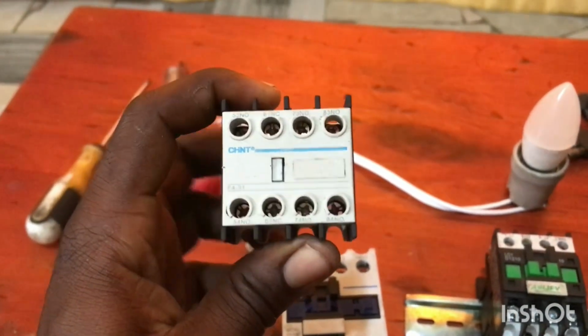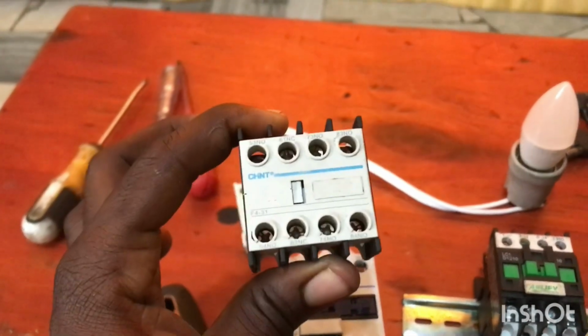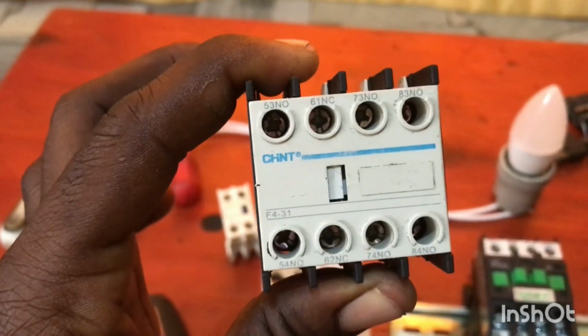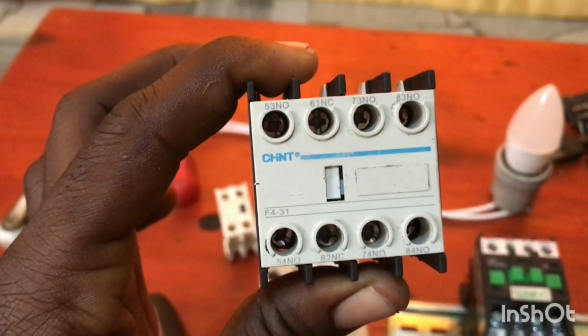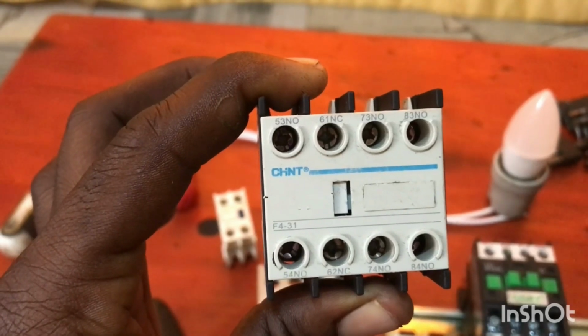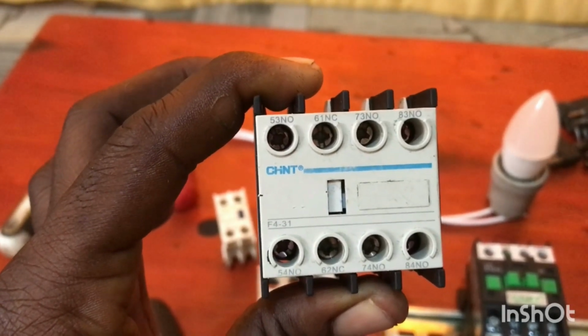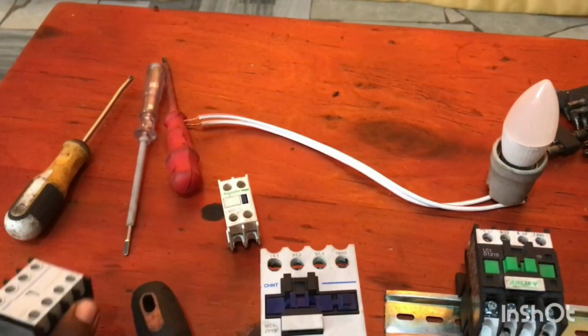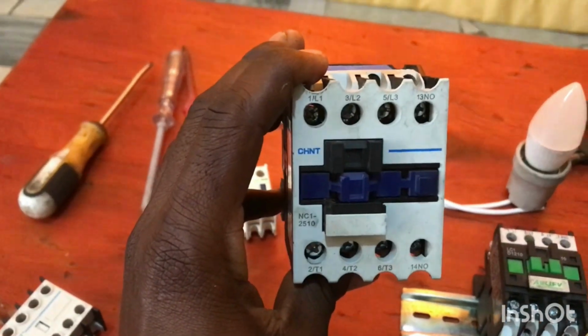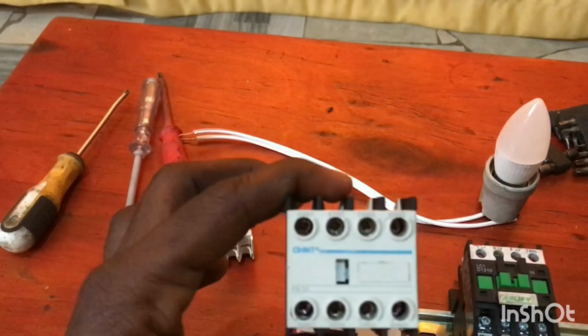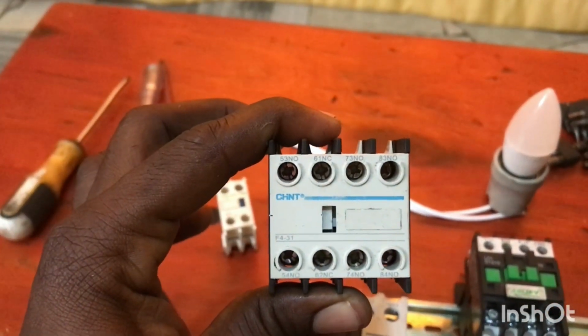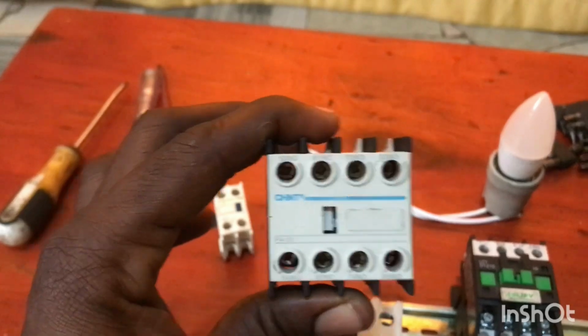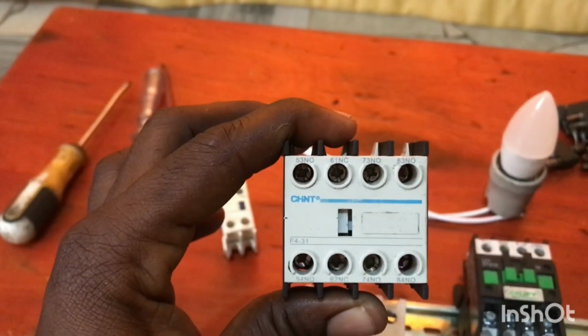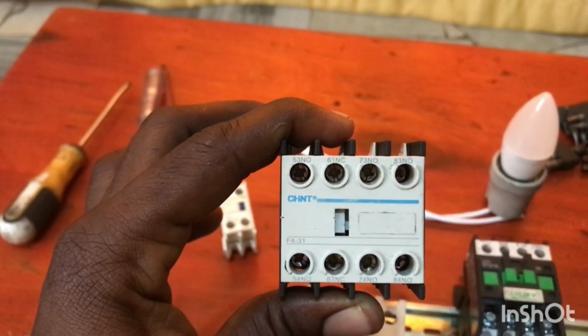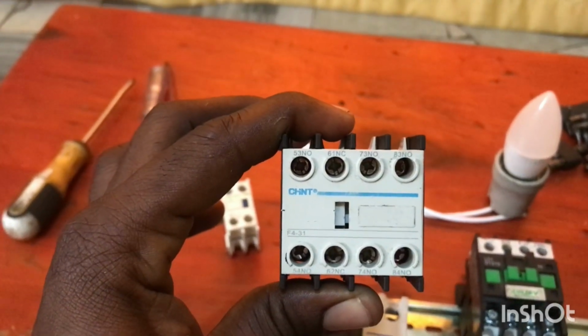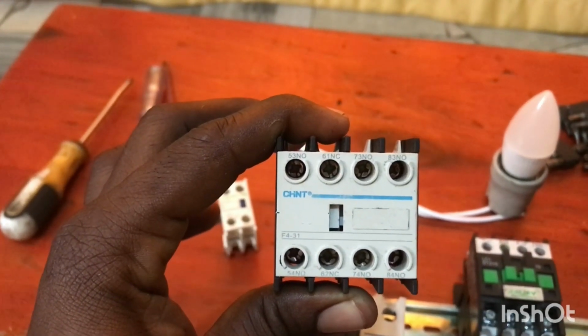For that contactor, it only has a normally open, but if we add an auxiliary, we'll increase the number of contacts, meaning we'll have more normally open and normally closed contacts, so as to increase the chances of making an automatic switch. So we are going to see how this auxiliary and the contactor work to perform an automatic operation, or to switch an appliance on or off automatically.